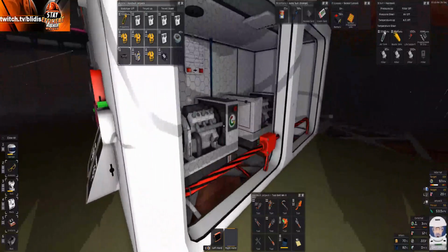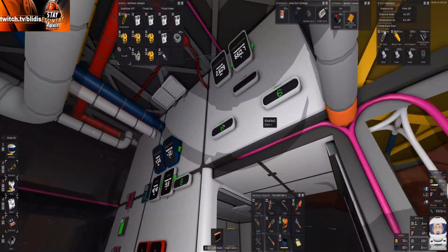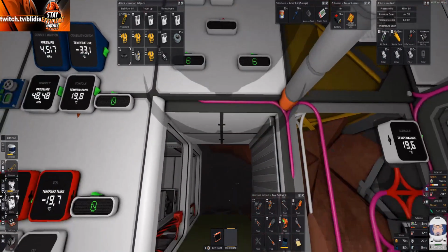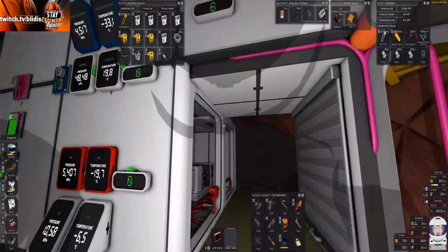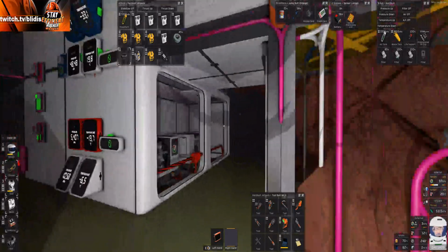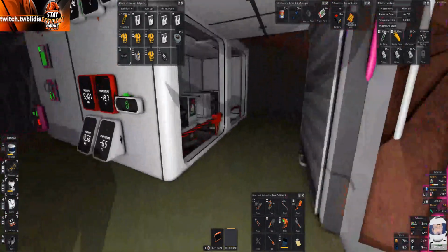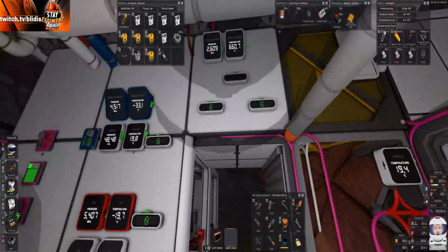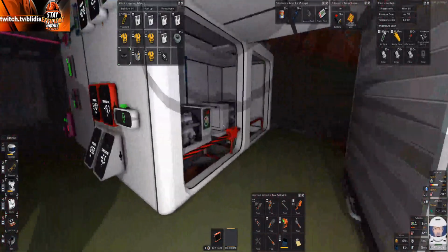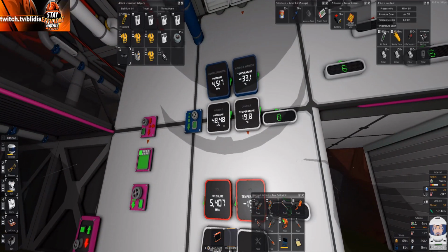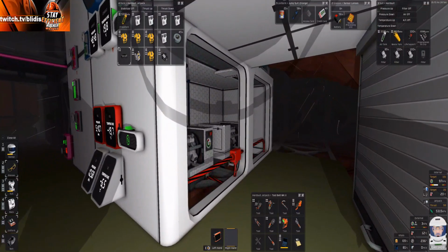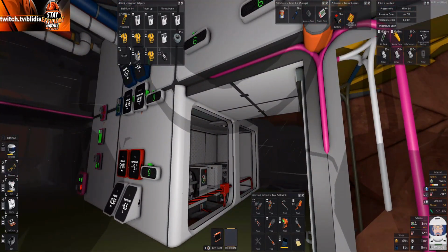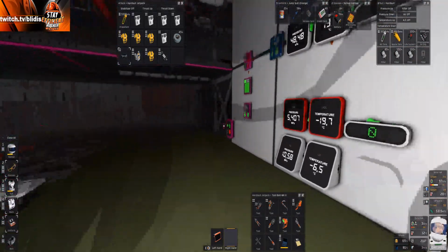It kind of works because the first generator starts when the first battery goes down, and the second one does the second battery when that goes down. If the second battery goes down too much, both generators start. I'm working on maybe making a little change to that program though. But yeah, it's working. Both generators can go for a long time with the environmental controls there, so there's no problem with overheating or overpressure in there. So it's fine. That's that program.